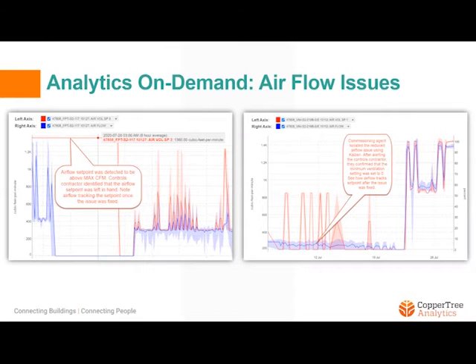This slide shows 2 examples of airflow issues identified through on-demand analytics. For both examples, we're looking at air volume set point, which is shown in red, and our airflow sensor, which is shown in blue. For the trend view on the left, we found that the airflow set point was manually overridden and was greater than the maximum CFM. You can see when the correction was made and where the set point drops to 0, and then afterwards when the airflow begins to track to set point.